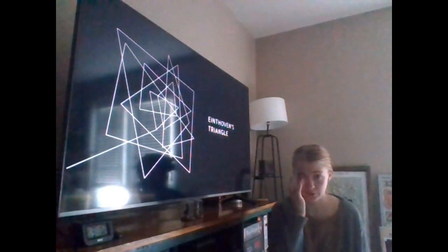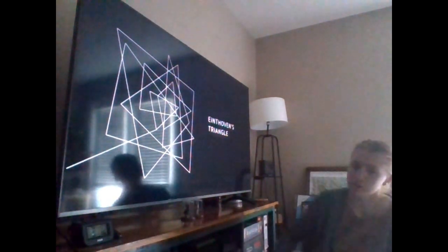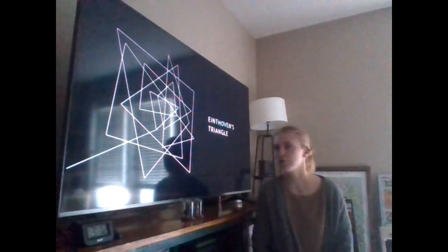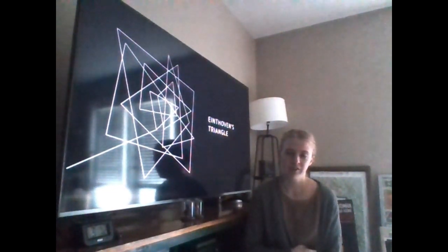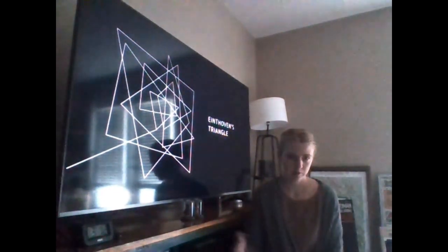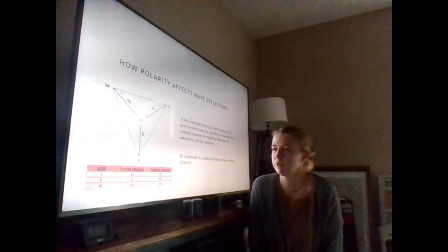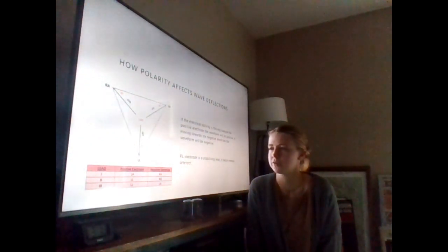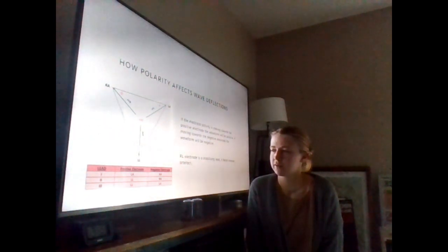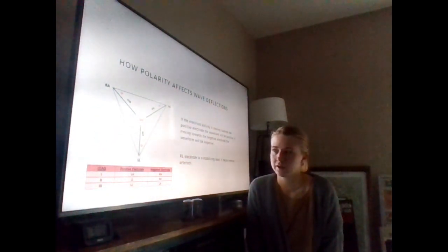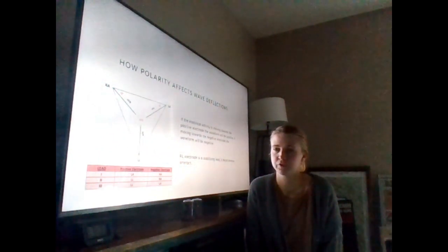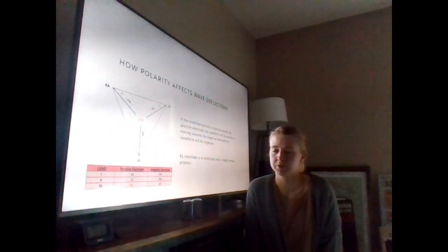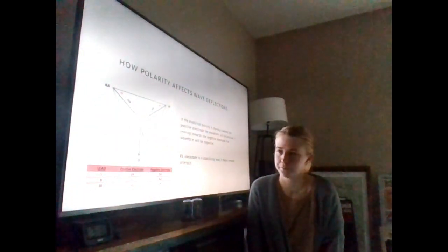So now we're going to go on to Einthoven's triangle. This is the theory or the law with your limb lead electrodes, how the positive and negative leads function to create their given outputs. So down below, you can see what electrodes are positive, what electrodes are negative. You'll note the right leg is not listed on there, as that does not factor into any of these leads. It's more just a stabilizing electrode that helps decrease our artifact.